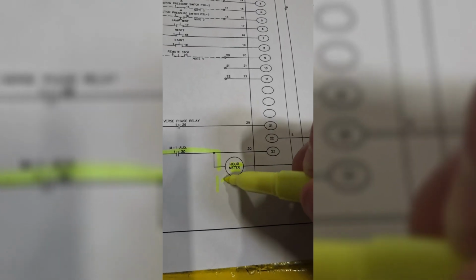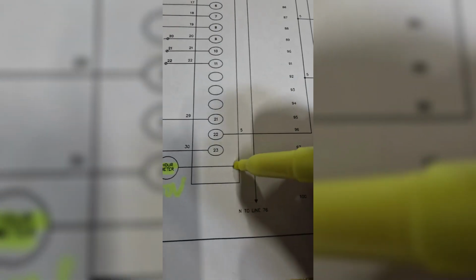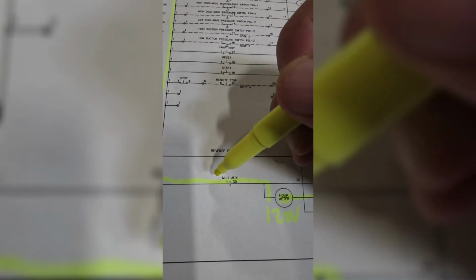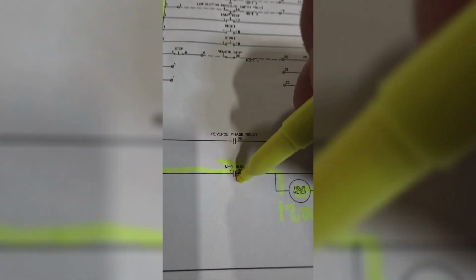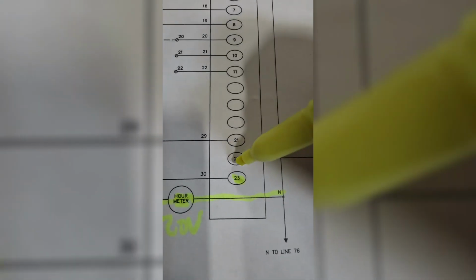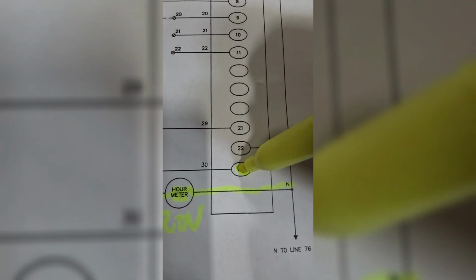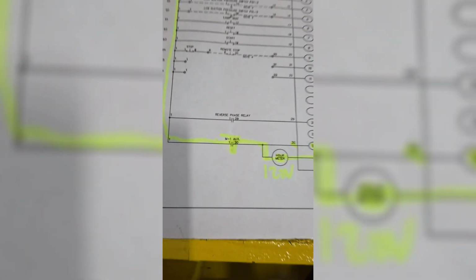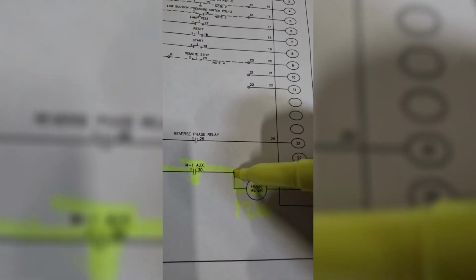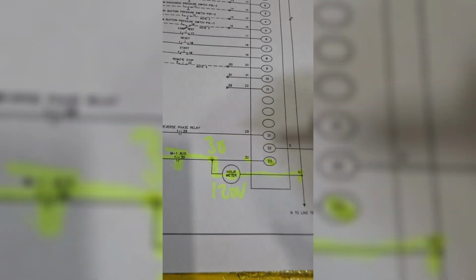This hour meter operates off of 120 volts. Here's the neutral side to your 120 volt circuit. This drawing is showing that when your M1 auxiliary contact is closed, it will start the counting on your hours meter. This also shows that your hours meter is coming into terminal number 23 and it's wire number 30 on your circuit. So we're looking for neutral and wire number 30. Now let's go open this cabinet and see what we can find.